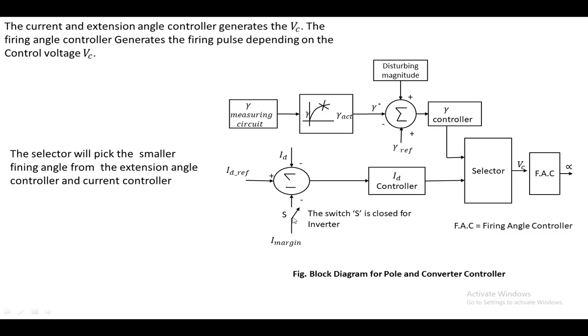A switch is included in the circuit. If we want to generate a firing angle for the inverter, the switch is closed, and the I-margin is added. For the inverter, the I-margin is subtracted from that value, and the result is given to the controller. Based on this value, the gamma angle is generated for the inverter circuit. Thank you very much for watching this video.